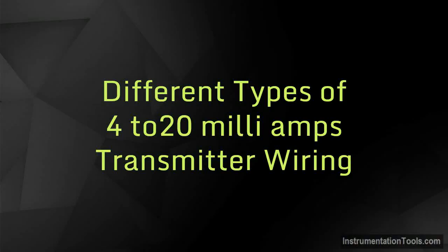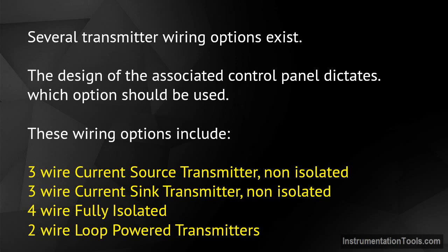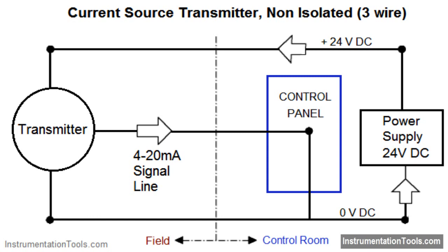Different types of 4 to 20 milliamps transmitter wiring. Several transmitter wiring options exist; the design of the associated control panel dictates which option should be used. These wiring options include: three-wire current source transmitter non-isolated, three-wire current sink transmitter non-isolated, four-wire fully isolated, and two-wire loop powered transmitters.